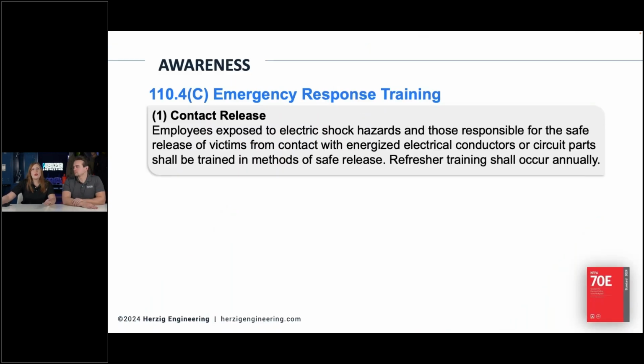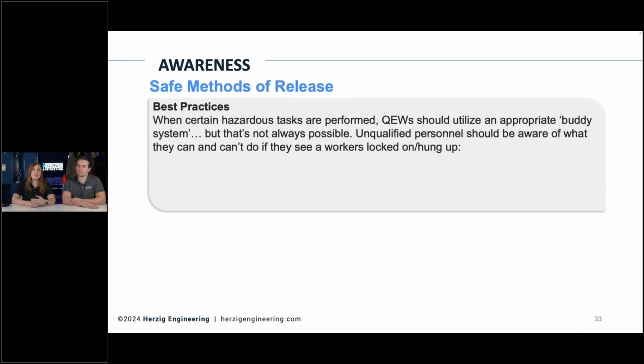Sometimes you also want to talk about contact release training. Specifically, for emergency response under 70E requirements, employees exposed to electric shock hazards and those responsible for safe release of victims from energized conductors shall be trained in methods of safe release every year. I'd argue even those not responsible for safe release, whose job duties don't expose them to shock hazards, should still be trained to some extent, since best practice is that qualified electrical workers use an adequate buddy system.